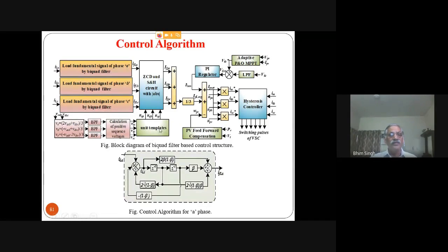This algorithm will work well in India, though it will work everywhere in the world, because normally in developed countries the voltages are not distorted and not too unbalanced. But here we might have unbalance as well as distortion. So this algorithm takes care, number one, of distortion, and another, of unbalance. We get a positive sequence voltage, and only then do we use it for calculating the amplitude as well as the template of the voltage, since the current we have to put in phase with that.